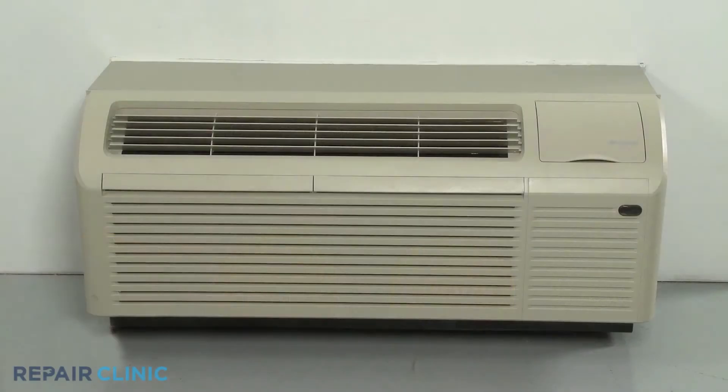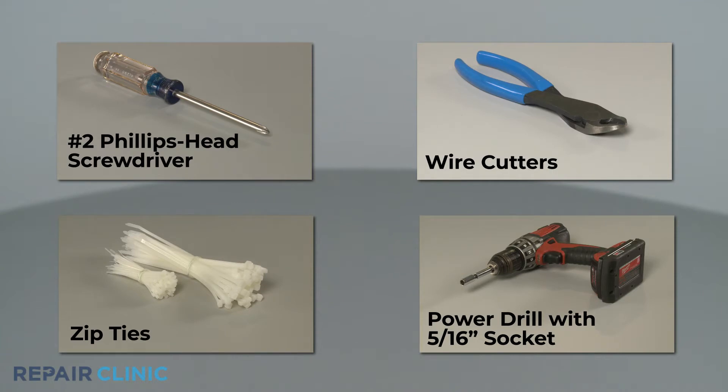Since Repair Clinic encourages you to perform this repair safely, a warning icon will appear when you should use caution. To replace the main control board in this Carrier/Gree ETAC heat pump unit, you will need a number 2 Phillips head screwdriver, wire cutters, zip ties, and a power drill with a 5/16th inch socket.